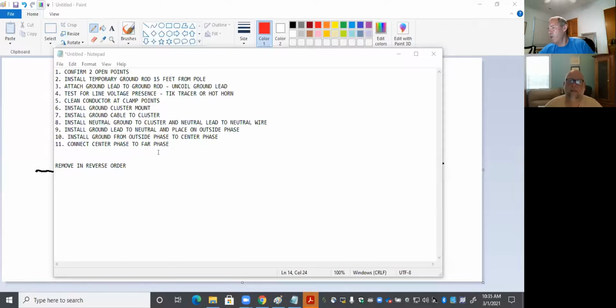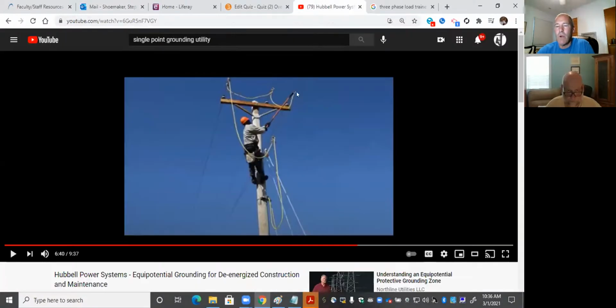All right, gentlemen, for the quiz today, you've got the steps to install. You're also going to include on that list the steps to remove. So you remove in reverse order. And when I say reverse order, it's not just disconnect center phase to far phase. You've got to come off in the process. I'll show you this picture right here, so that every time you handle the jumper that you're removing, it's grounded.